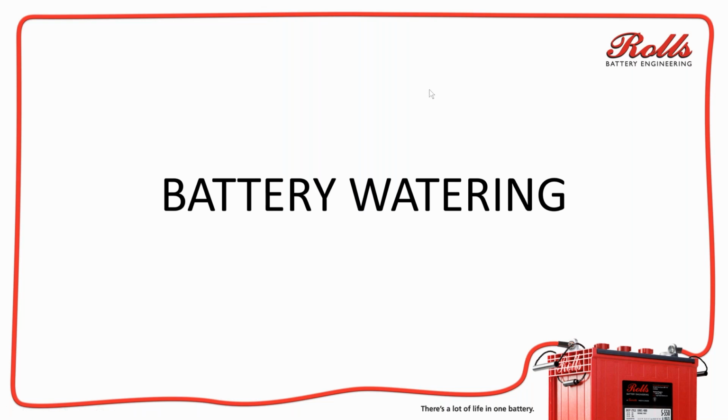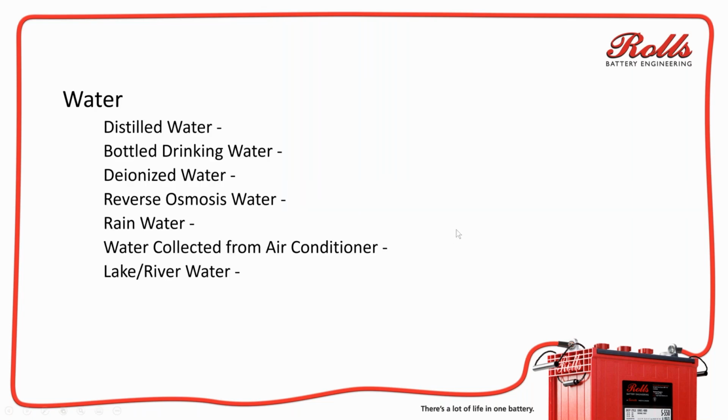So on battery watering, especially flooded lead acid batteries, water is not created equally. Here's a list of waters that a lot of customers will use: distilled water, bottled drinking water, deionized water, reverse osmosis water, rainwater, water collected from an air conditioner. That's one of my favorites. You get that a lot in the Caribbean and Africa, where they'll sit a bucket under the air conditioner, let the water drip into it, and then put that into the batteries.